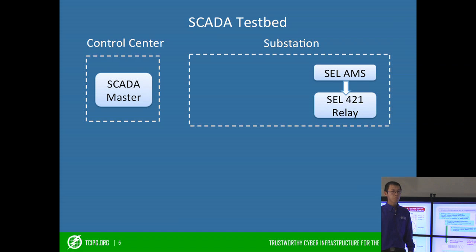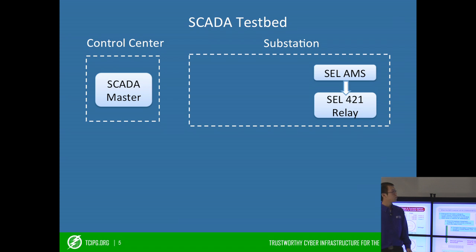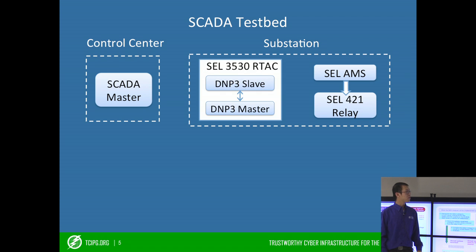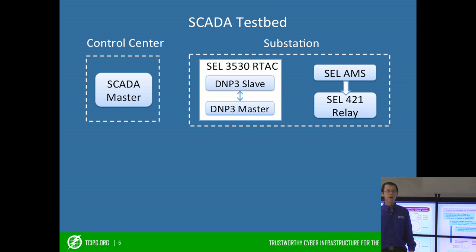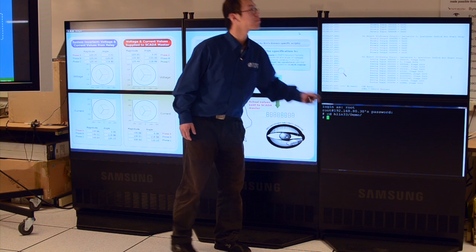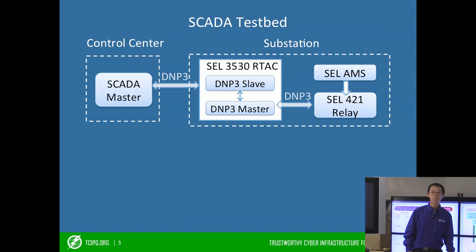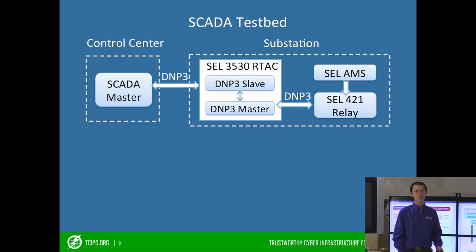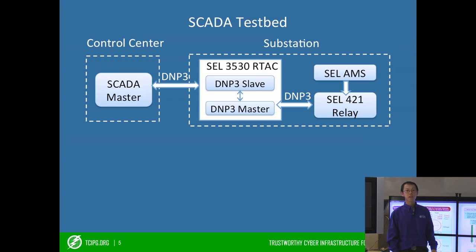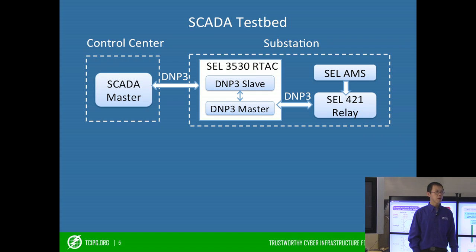The SEL AMS simulates an electrical line. It will produce voltage and current signals to the SEL 421 relay. The SEL 3530 RTAC is a data aggregator, and this is shown on this screen. It contains two software components: the DNP3 master retrieves the measurement data from the relay, and the DNP3 slave expects DNP3 requests from the SCADA master and replies with the collected measurement data.